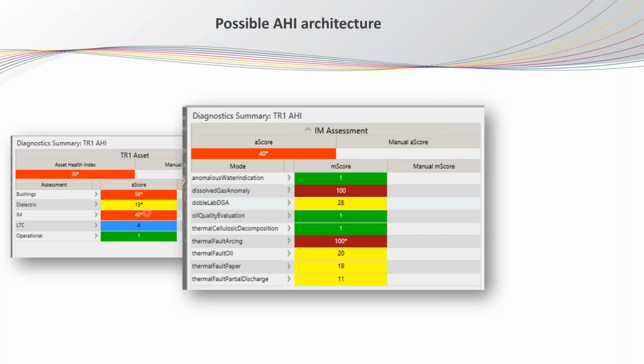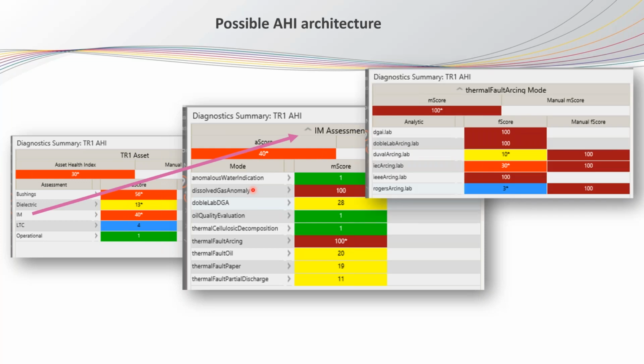When you click on the insulating material, you are going to see the different failure modes. We can say here that the thermal fault and arcing are high, so it means that C2H2 is high, and the dissolved gas anomaly and the total dissolved combustible gas are also quite high. We can even go to a lower level and look at the different analytics and the different standards, and identify why this transformer has a high asset health index based on the lowest level of analysis.